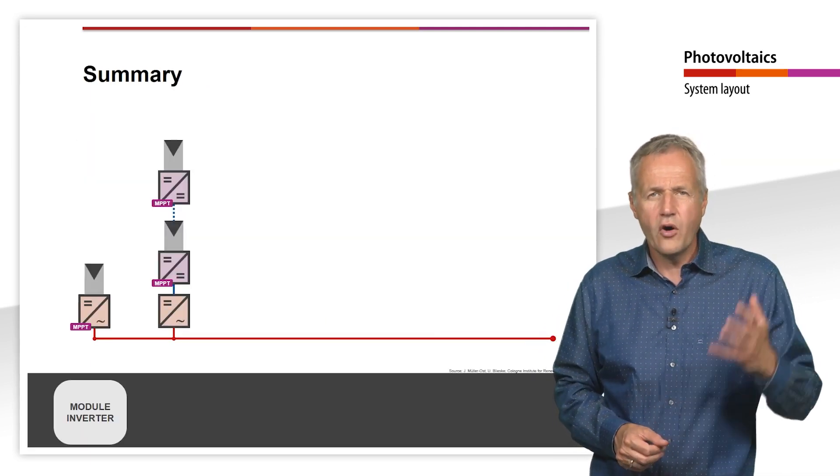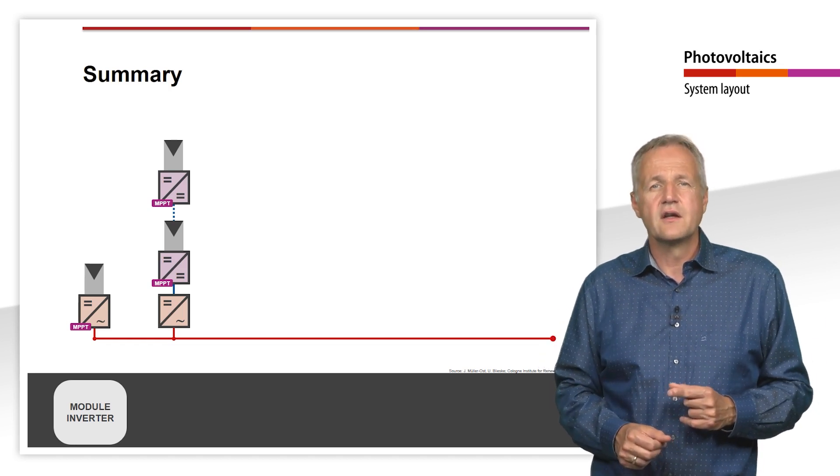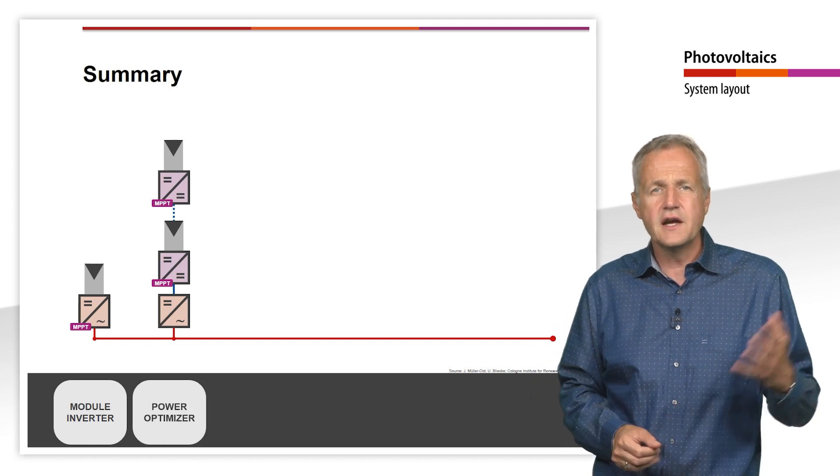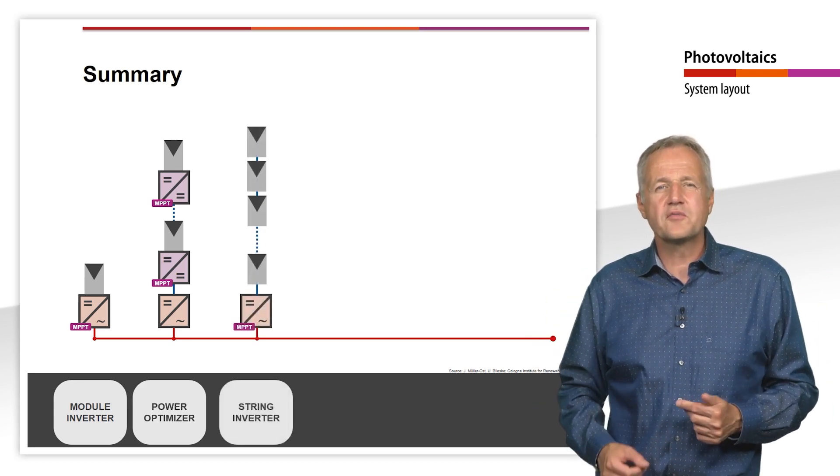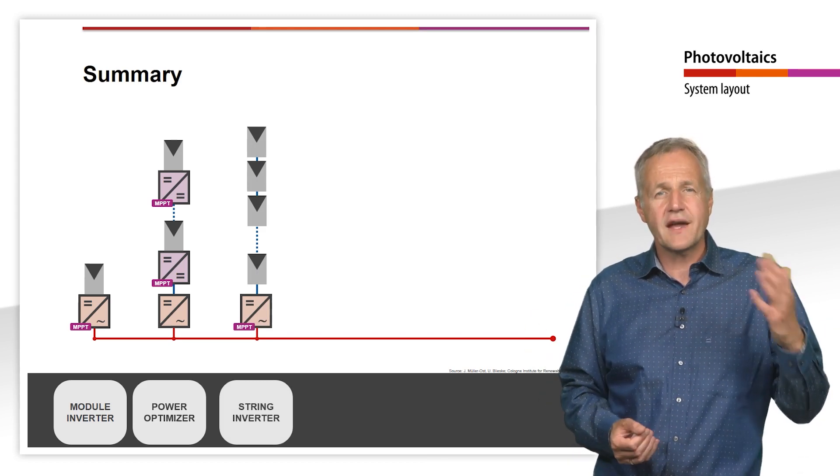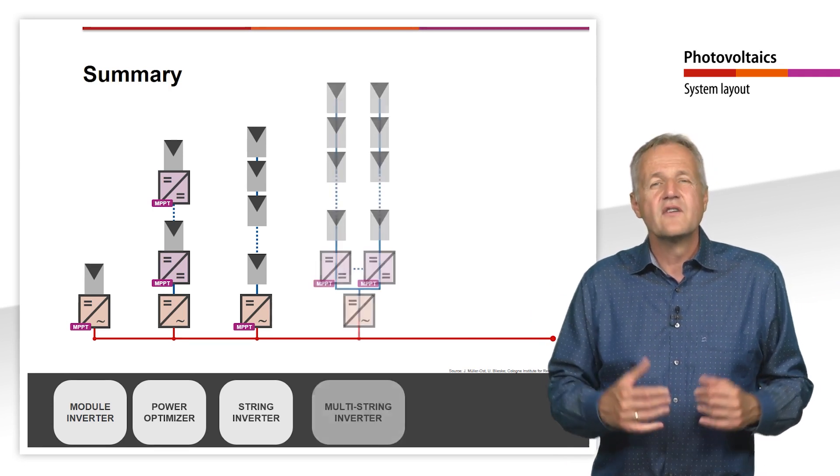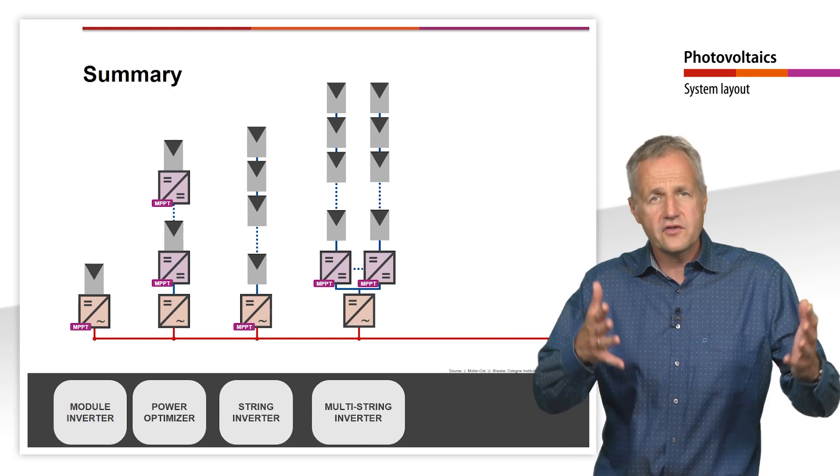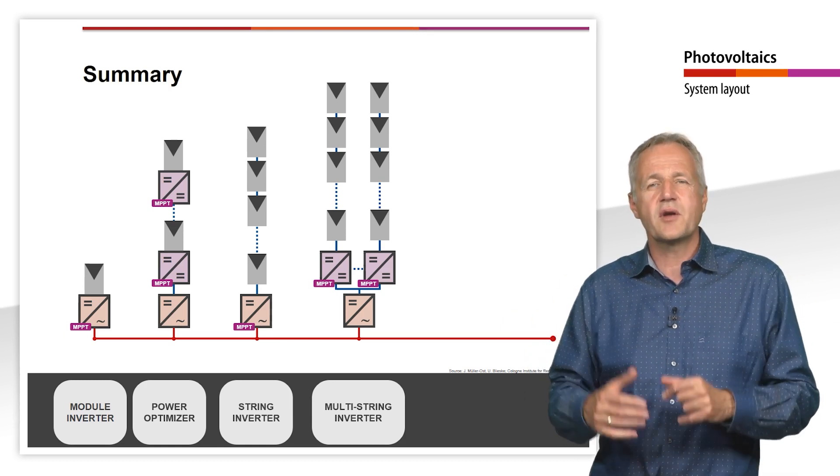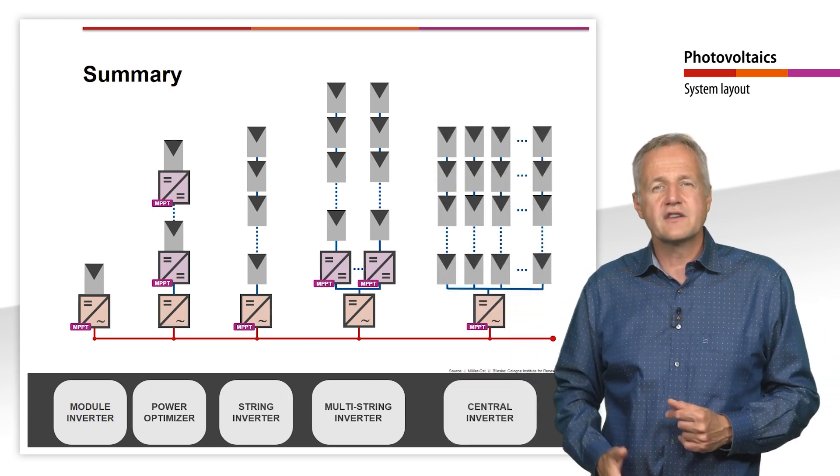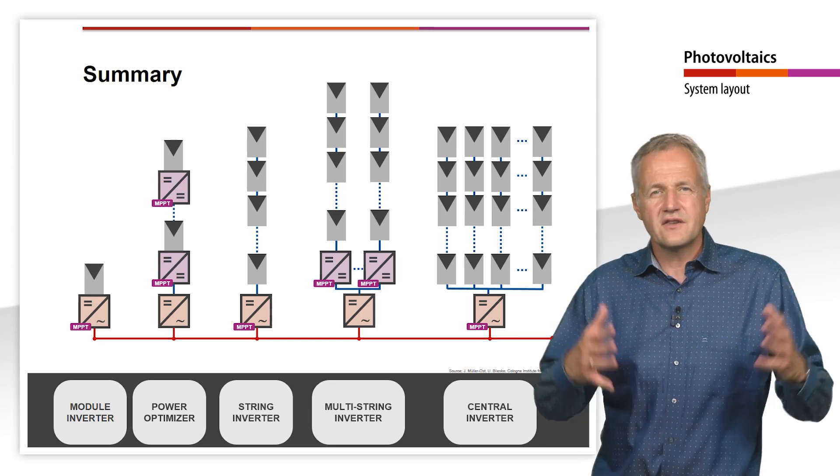Let's summarize what we have learned. The smallest inverters are module inverters, which are especially useful in systems with few modules and different orientations or shading. The string inverter is most commonly used for small systems. Here, all modules are connected to form a string and operated at the same operating point. The power optimizer concept combines the advantages of module and string inverters. In this case, MPP tracking takes place on the module level, but conversion to AC takes place in a string inverter without MPP tracking. With increasing plant size, multi-string inverters are used instead of string inverters. Here, the MPP of the different strings is determined individually, but the conversion into alternating current takes place centrally. Very large systems are operated with one or more central inverters. Several module strings are connected in parallel for this purpose. All modules are operated at the same operating point.